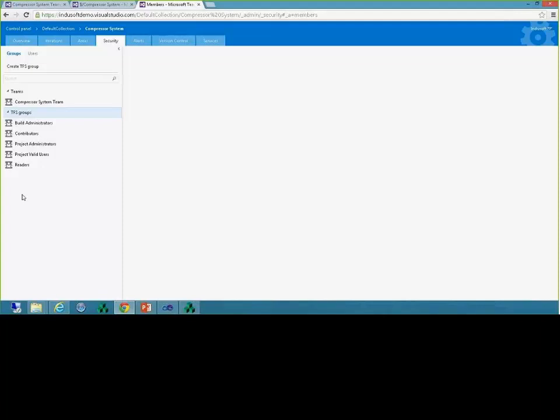It gets modified because that's the tags database. So if you have 7 or 8 users working at the same time and adding tags, the tag list will get modified because of that. Also, if you configure alarms or trends, that's also information that gets stored into the tags database, and that's why. But the merge tool should help you.